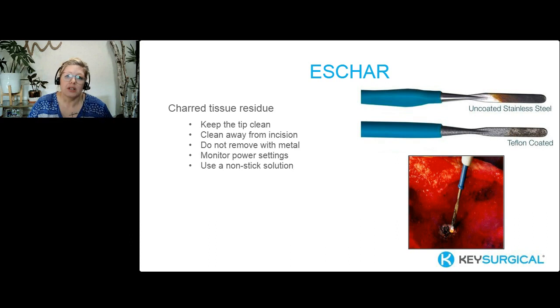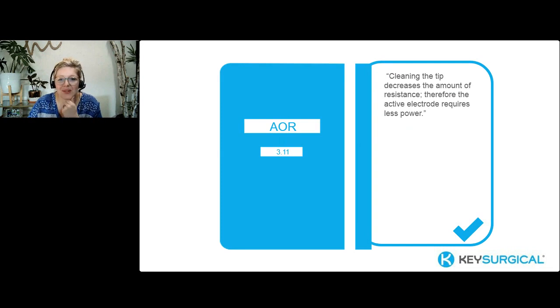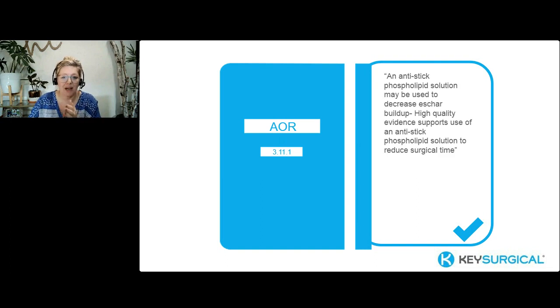Finally, you can use a nonstick solution. AORN 2021 updated their guidelines and said you can use an anti-stick phospholipid solution on your devices, coated or uncoated, to prevent that eschar buildup and reduce the number of times you have to clean it off. This is the AORN guideline, and it supports everything we just said. Cleaning the tip decreases the amount of resistance. Therefore, the active electrode requires less power. So that's monitoring those power settings. Again, AORN guidelines, this was the update in 2021. I was just reading the 2022 that was coming out, so I'm halfway into 2022 already. Maybe everybody is, but an anti-stick phospholipid solution may be used to decrease eschar buildup. And then they have some really high quality evidence that supports that use.